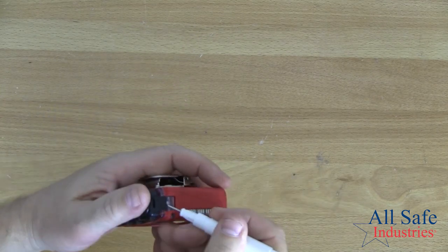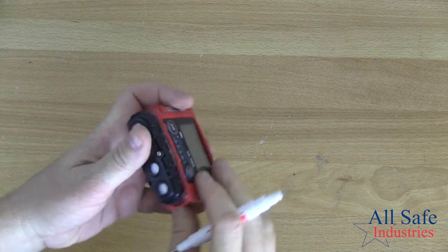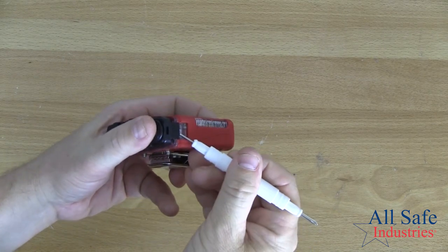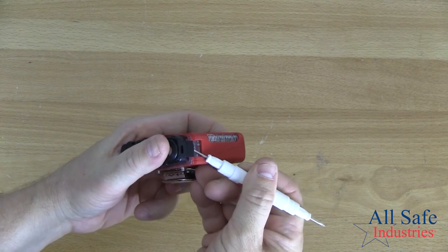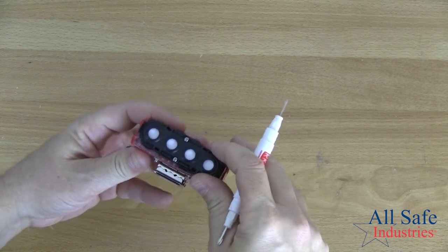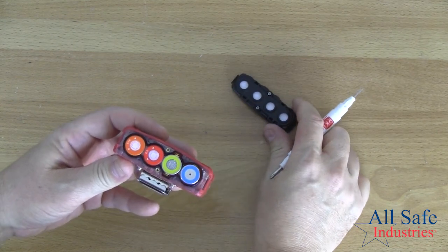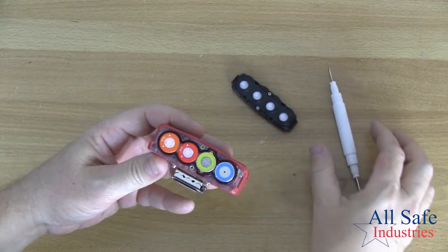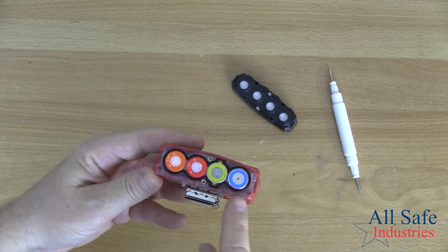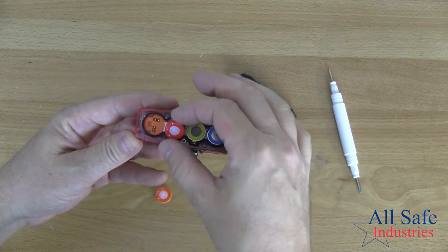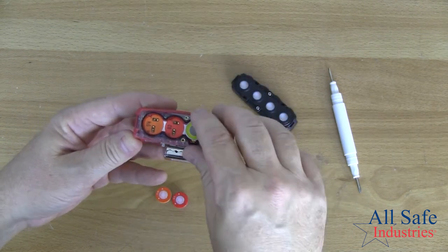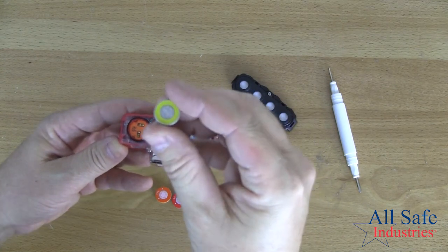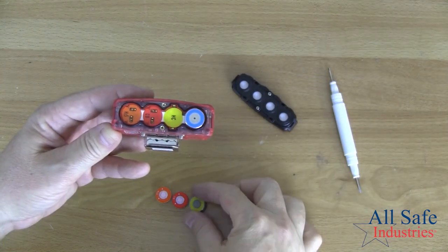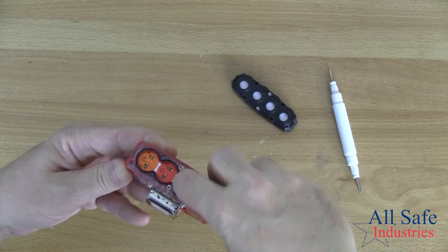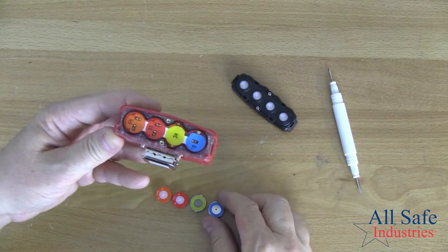And then there's 2 little clips on the side, so I'm just going to pry that up on one side, and then I'm going to pry this up on the other side. And now my sensor retainer is loose. I'm just going to pull that and set that off to the side. And here you see my 4 sensors, and they just literally sit right there. Here's my H2S sensor. Here's my CO sensor. Here's my LEL sensor. It's the only one that has the metal sintered filter on the top. And here is my oxygen sensor. You can see that these sensors are color coded.